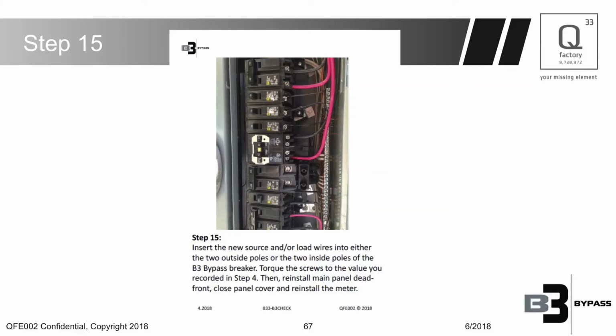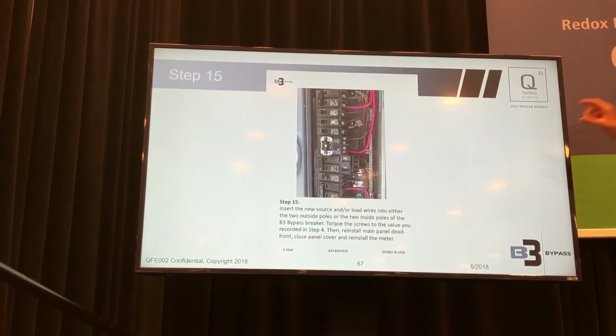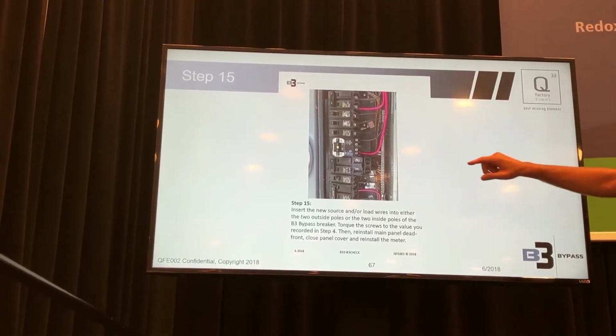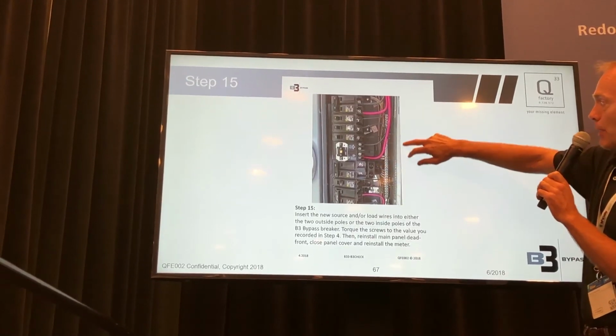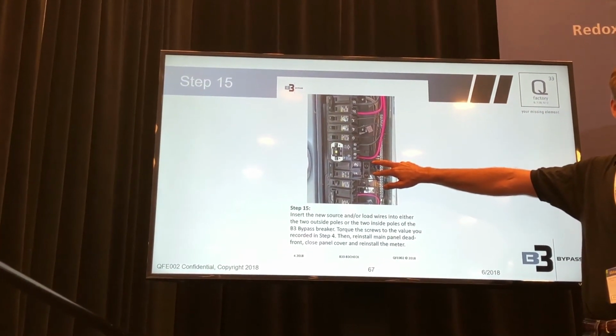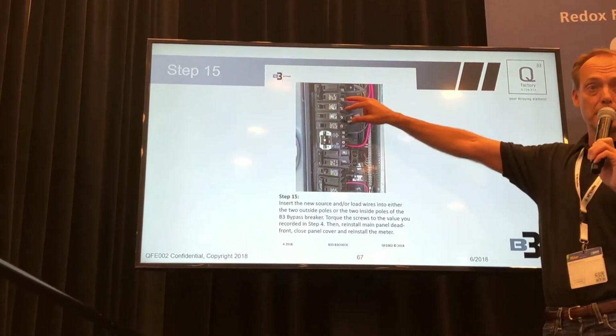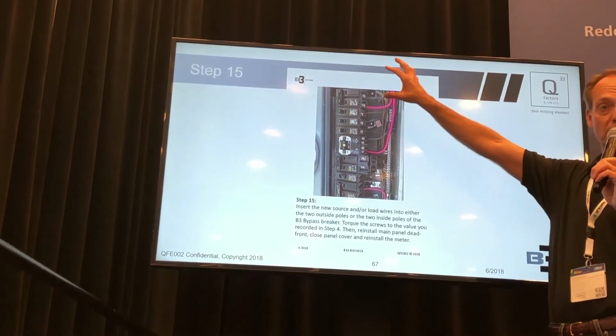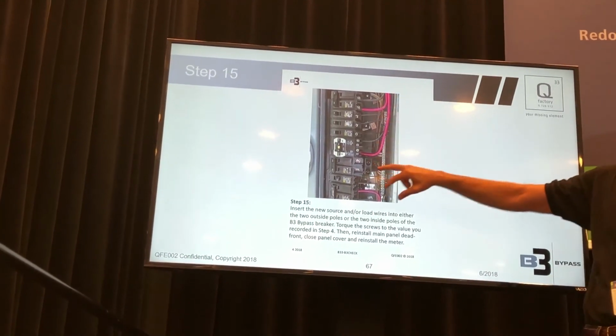It's pretty straightforward. The magic to it, once you get a bit more experience, is wedging it in there, because you have to get it underneath the feeder wires and you have 2 inches of space to pop it in. The key thing is marking where you're going to strip and using the right tool. Use the Q stripper tool so you get a clean strip and you're not nicking any strands of that feeder wire. If you want to position it somewhere else, you would run a jumper cable from the split lugs using the post adapter to where the main breaker is. If you do have a fixed main, you could use those jumper cables.